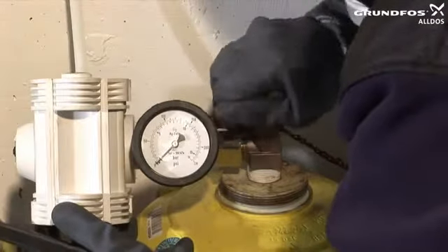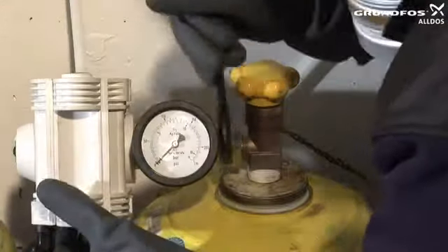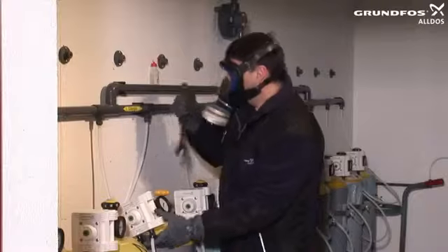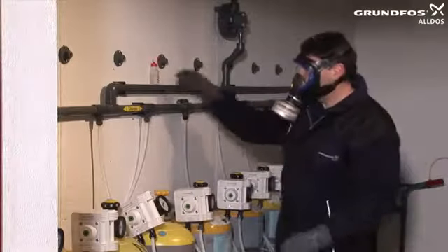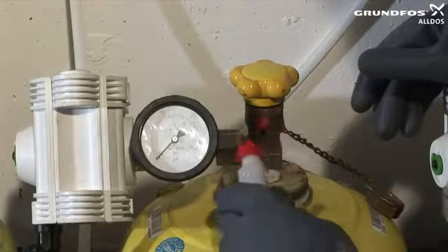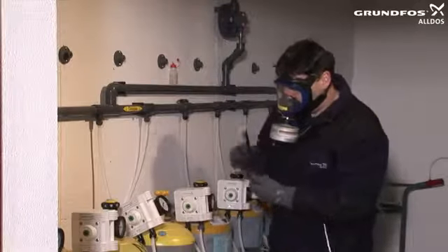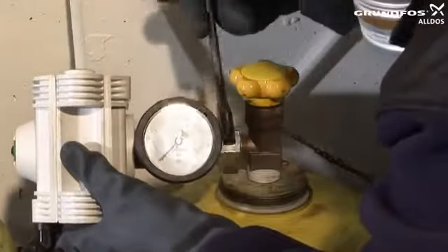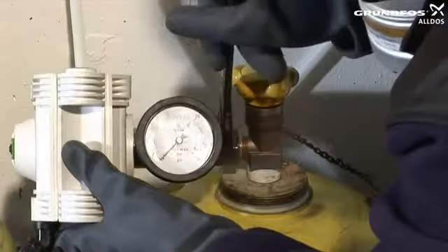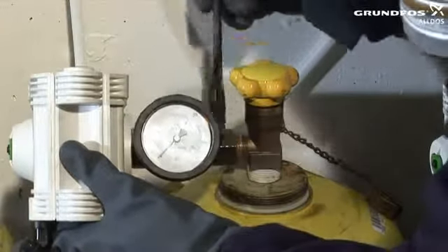On a cylinder which is to be replaced, first close the main cylinder valve. The manometer should now indicate zero. Loosen the lock nut on the armature by about half a turn and carry out an ammonia test in close proximity to check for leaks. Hold the ammonia bottle upright and ensure that the ammonia does not come into direct contact with the valve or other components or pipework, as this could lead to corrosion and deterioration of the parts. Under no circumstances should you remove the lock nut entirely, as this could prevent it from being tightened quickly and easily in the event of a leak.